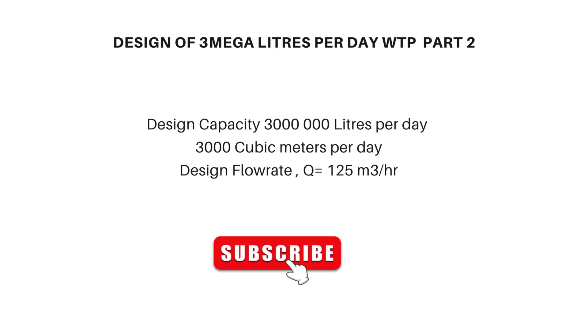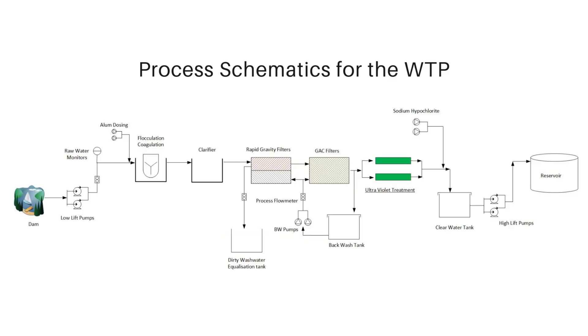So our design flow rate that we will be working with from now onwards is 125 cubic meters per hour. This means we are going to size everything in this design — from the flocculation tanks to the clarifier, the filters, and even the pipework — all based on that flow rate. The flow rate is also used to calculate how much chemical we are going to be dosing into the water.